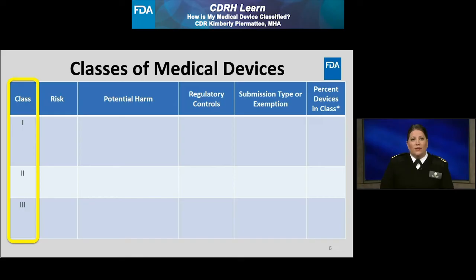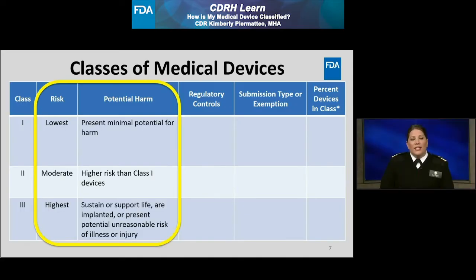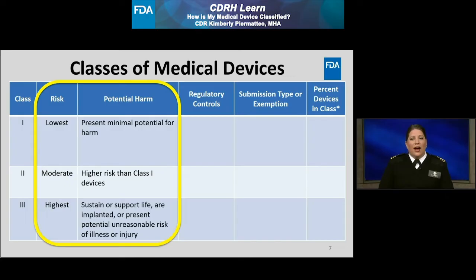As I discuss each class of medical devices, I will fill in the middle columns of this table. The columns are titled device risk, potential harm, as well as applicable regulatory controls and submission types or exemption for each device class. Class 1 devices are considered to be the lowest risk and present minimal potential for harm to the patient or user. Class 2 devices are considered moderate risk and present a higher risk than Class 1 devices. Class 3 devices are considered the highest risk, and these devices may sustain or support life, be implanted, or present the potential for unreasonable risk of illness or injury.